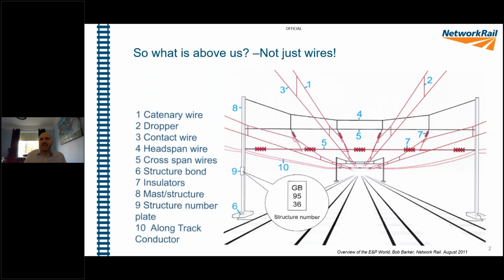Not everything's all connected together, and the simple reason for that is that when we have a fault, we don't want everything to go off. We don't want to have all trains on all lines stop if we have a circuit breaker trip. So you can see across the span wire, the insulators are keeping the different tracks apart. They're also keeping the live equipment, or the equipment that's at 25,000 volts, away from the equipment that is earthed or connected to traction return. So you can see the example here, the top 2 wires that form this headspan have got no insulators between them and the masts, and that's a really good indication that they're at earth potential or connected to the traction return system.